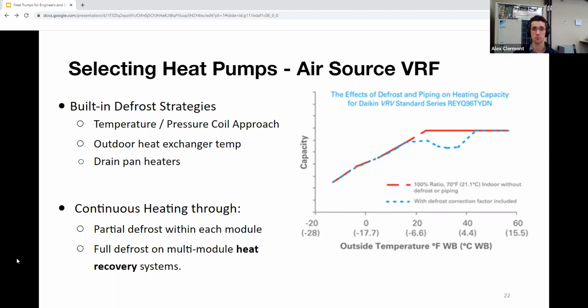So any air source machine is going to form frost on its outdoor coil if it's doing heating in our climate. Now, the machine is really intelligent and knows how to get rid of that frost. It switches the cycle over and warms up the outdoor coil to melt that ice. Now, how does the machine know when to do that? It looks at its heat exchanger pressures and temperatures to know how good the machine is doing at exchanging heat.